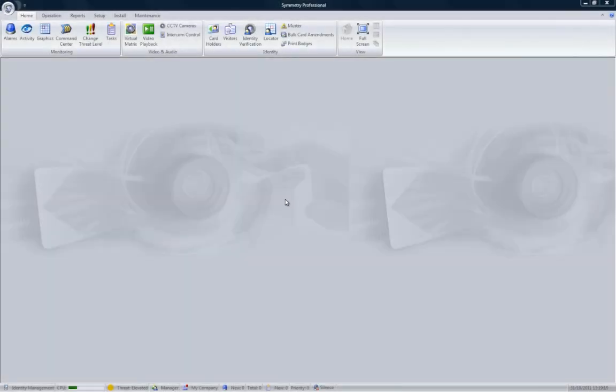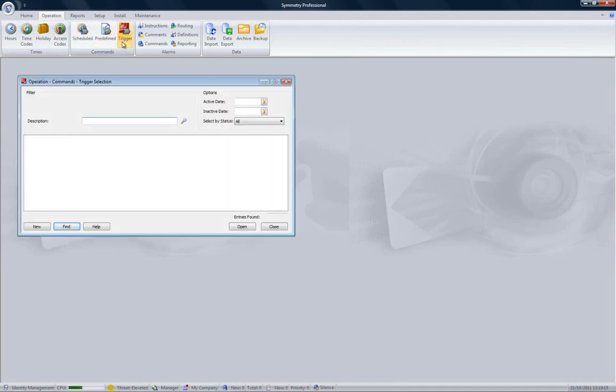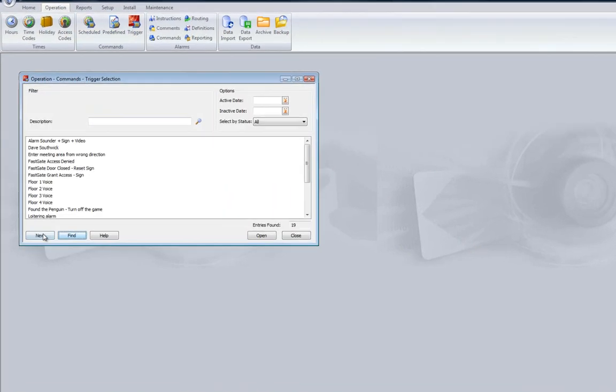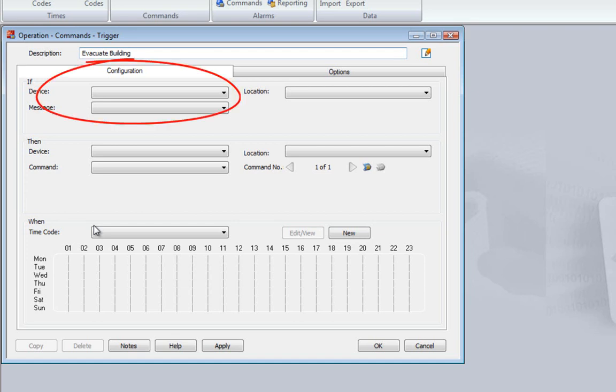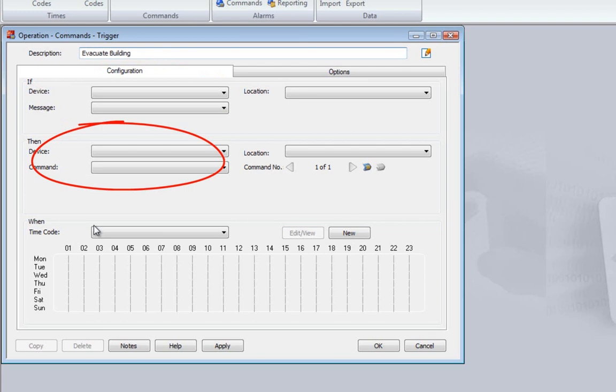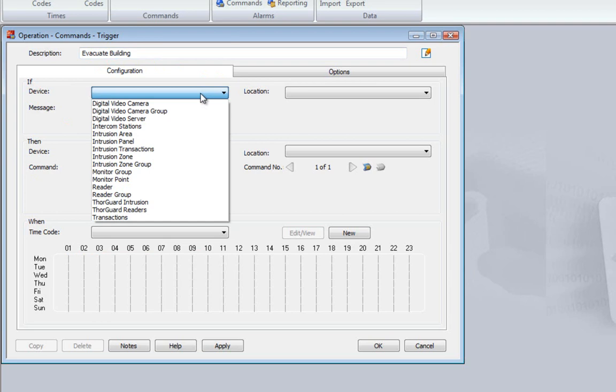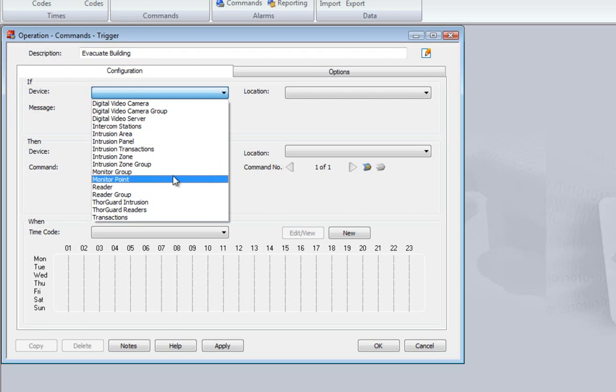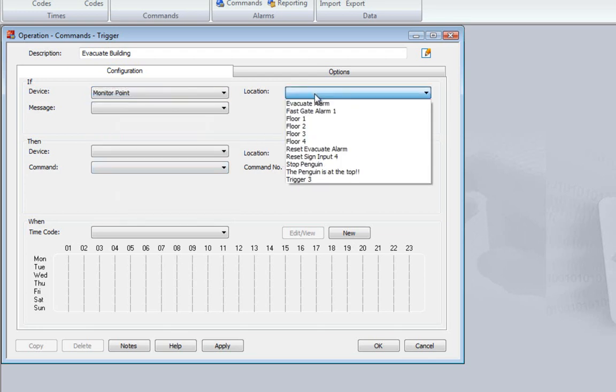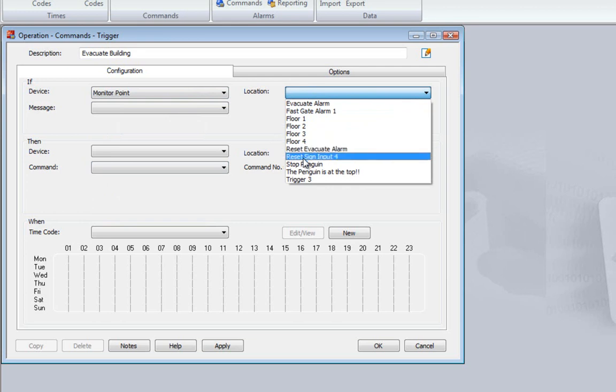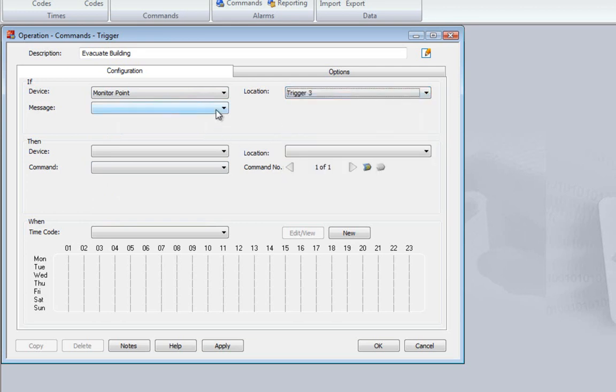To show how flexible symmetry can be, we're going to set up a trigger command so that when something happens, it automatically triggers some other events. Select Operation, followed by Trigger, and then click the New button. The next screen shows the If, Then, When format of the trigger command. Once we've entered a description, we can then describe if something happens, then something else is to happen, and when it should happen.